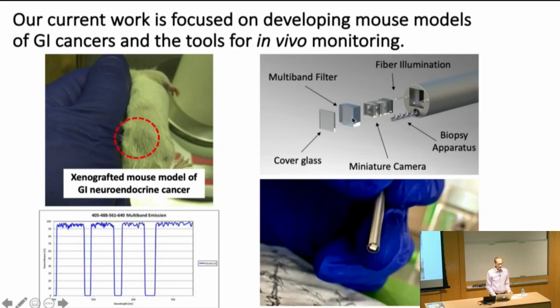of it. And so this thing we specifically picked so that it could let you do 4 different types of fluorescence imaging, not necessarily simultaneously, but kind of in series. You can just cycle through different illumination wavelengths and excite different fluorophores. And so you can see that the transmission of this filter dies off about 405, and so that's a common fluorescent wavelength, at 488, 561, and then 640. And so we can use those 4 different wavelengths to track up to 4 different labeled cells.